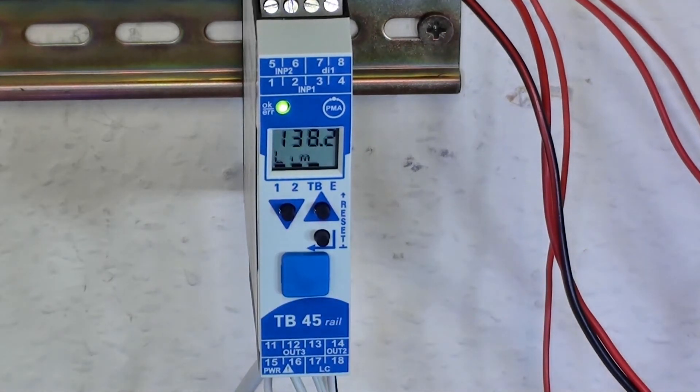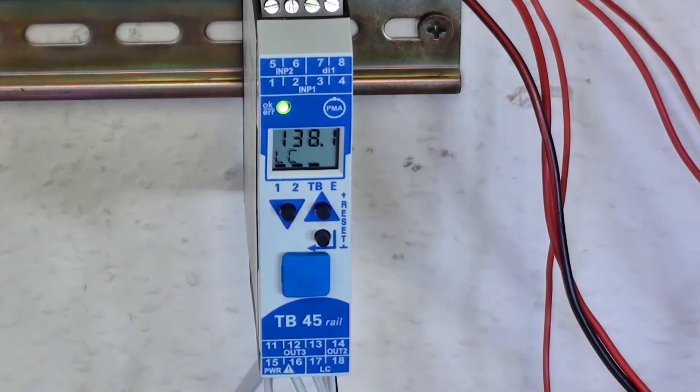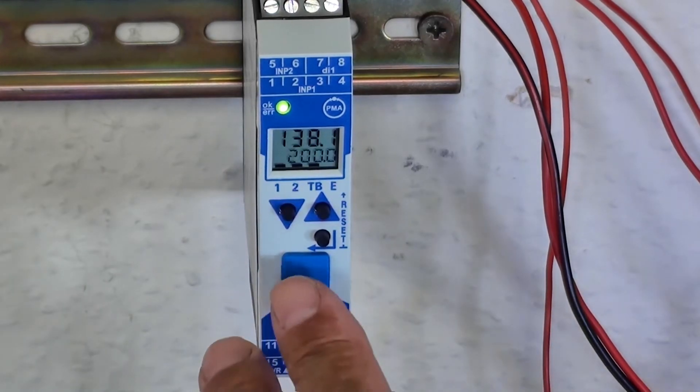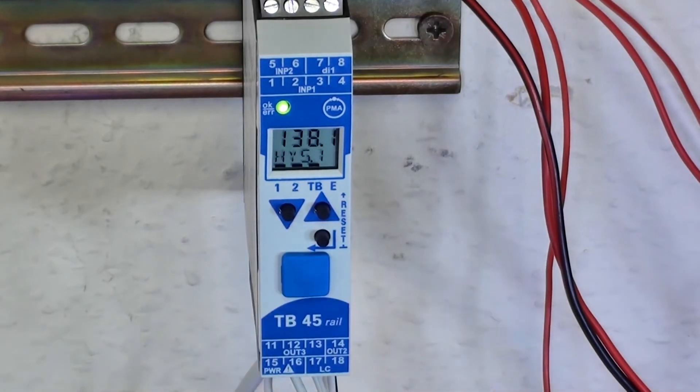The first parameter it shows is LIMIT. LC, this is the limit alarm, the exceed limit alarm value. And I have it, I've programmed it for 200 degrees C. And also with a hysteresis of 5 degrees C.